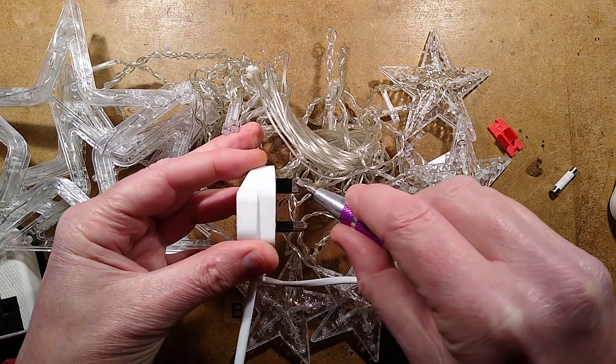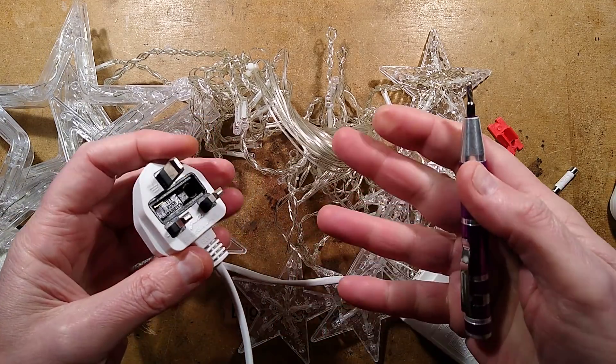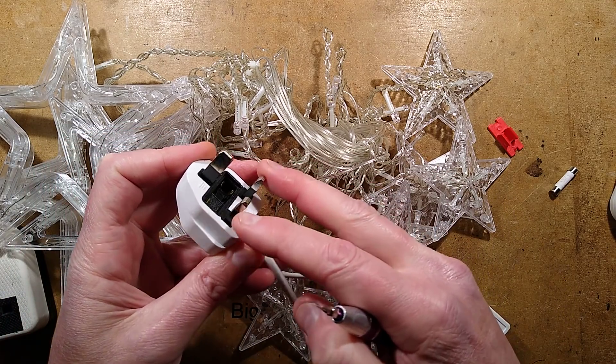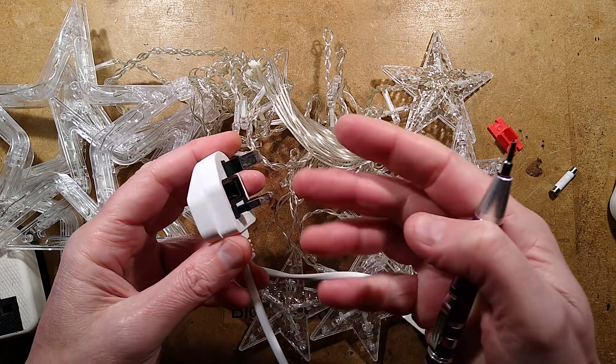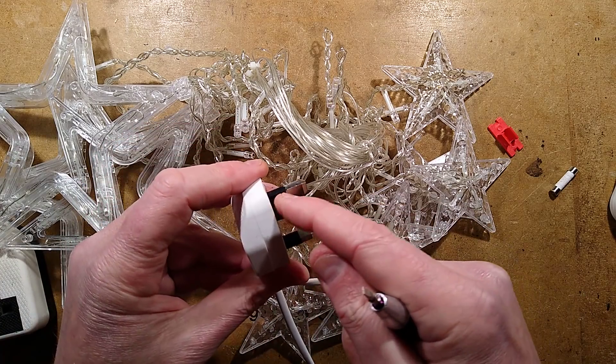The earth pin has that plastic spacer on it, which it's not so critical in this instance, since it's really just been used to open the shutters for the live and neutral. But if that plug was used in an actual earthed appliance, it would not be good because it wouldn't make a connection.